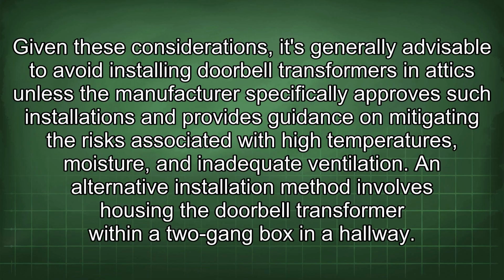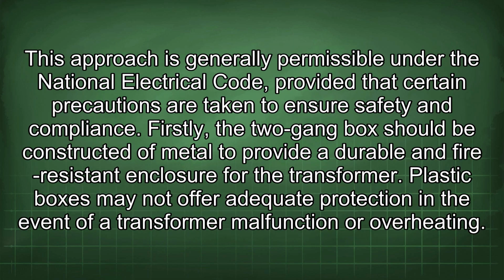Given these considerations, it's generally advisable to avoid installing doorbell transformers in attics unless the manufacturer specifically approves such installations and provides guidance on mitigating the risks associated with high temperatures, moisture, and inadequate ventilation. An alternative installation method involves housing the doorbell transformer within a two-gang box in a hallway.